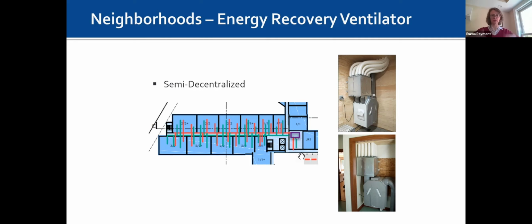So we're running these in our corridor ceilings, adding more stuff to coordinate in our corridor ceilings, and it requires balancing. Because we've got a 2-bedroom, 2-bath here and a 2-bedroom, 2-bath here. They both need the same amount of CFM, but they're at different points in the duct run. Static pressure is what it is. So we need some sort of regulating damper, constant air regulator, or balancing dampers of some sort on these to ensure that we are exhausting what we required and providing fresh air as required.